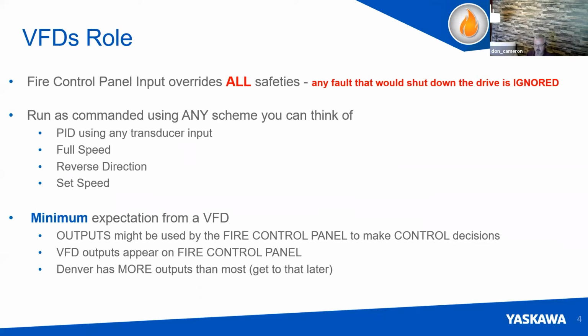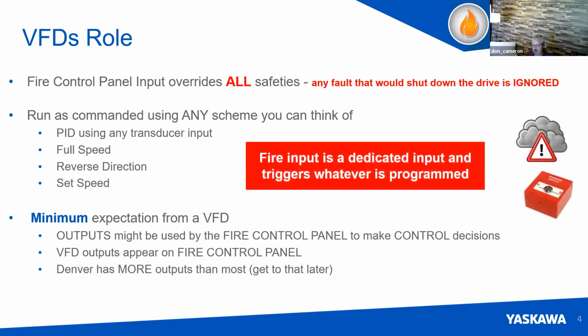So the minimum expectation from a VFD is that the outputs are going to be used by the fire control panel. It could be to make control decisions, or maybe not, but the outputs will also appear on that fire control panel. And the good news for you guys in your backyard is that Denver has a more rigorous structure for fire mode outputs than most, but we'll get to that in a minute. Again, a fire input is a dedicated trigger, and whatever you program it to do, it's going to do, and it will run to destruction.